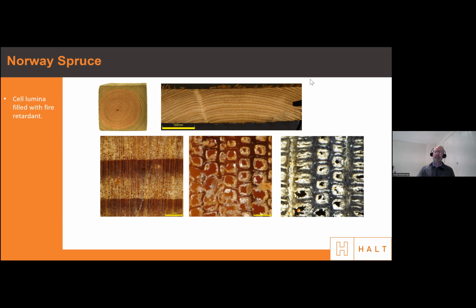If timber is impregnated with a classification of BS1D0, it maintains that same fire classification until the timber starts to decay. So logically, the fire retardant becomes part of the timber — if it's used externally and over a 5, 10, or 15-year period begins to rot and decay, the fire retardant will rot and decay along with it. It is a through-and-through process. Looking at these microscope pictures, we can see the fire retardant deposited through impregnation becomes an actual part of the timber structure itself.